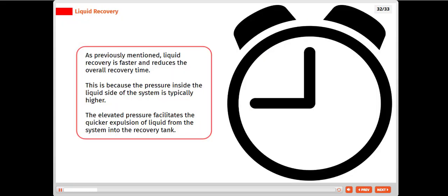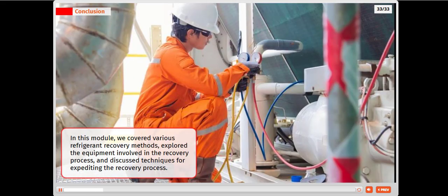As previously mentioned, liquid recovery is faster and reduces the overall recovery time. This is because the pressure inside the liquid side of the system is typically higher. The elevated pressure facilitates the quicker expulsion of liquid from the system into the recovery tank. In this module, we covered various refrigerant recovery methods, explored the equipment and recovery process, and discussed techniques for expediting the recovery.